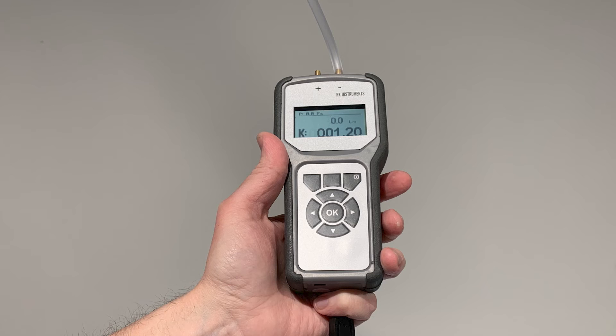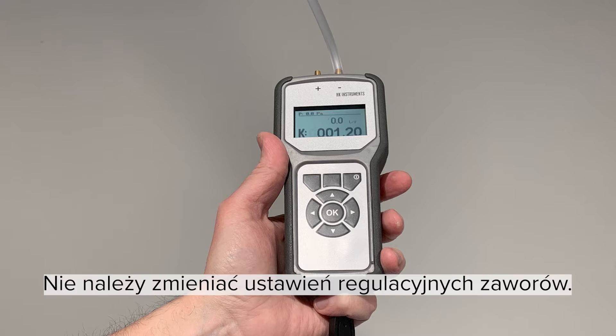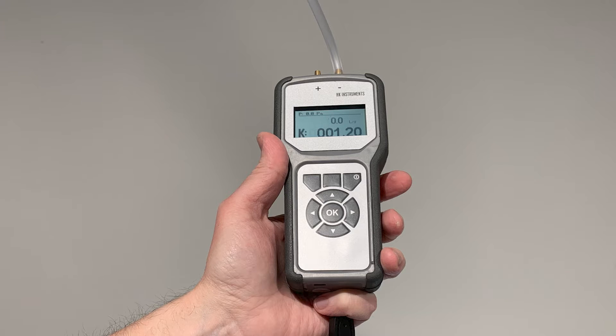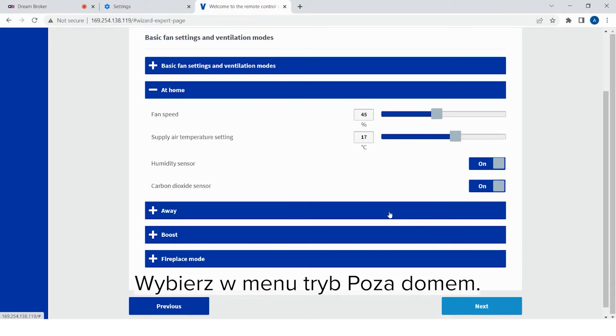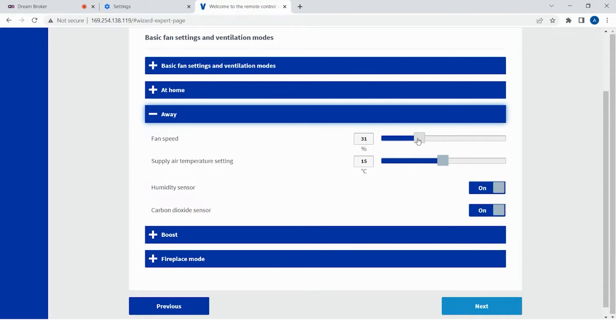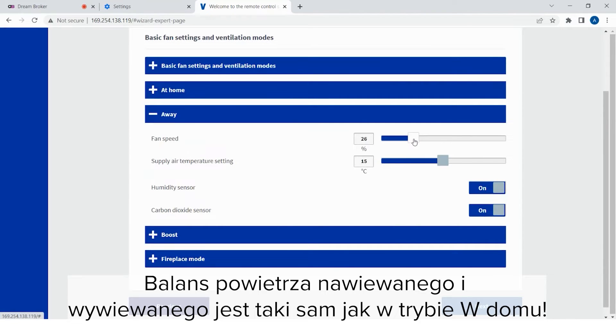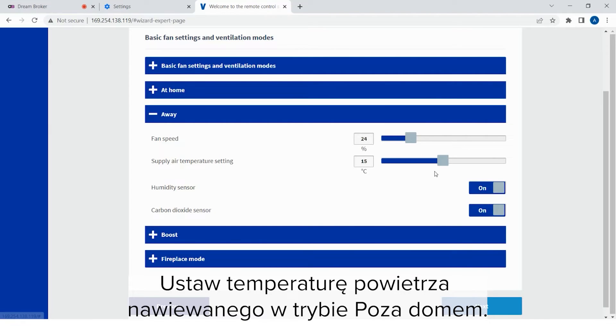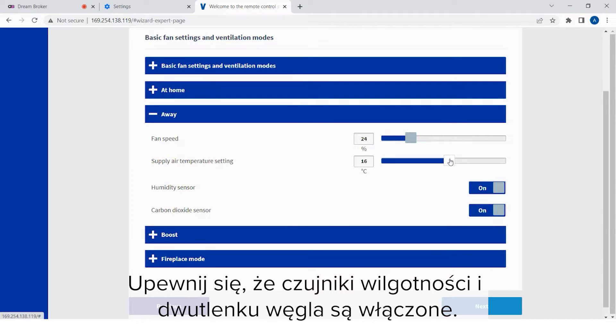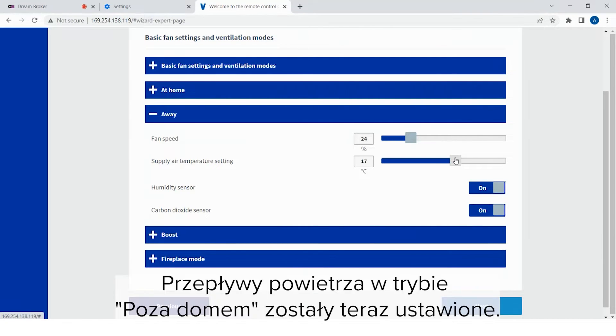Ensure that the humidity and the carbon dioxide base controls are turned on. Adjust the supply and the extract air flows of the away mode. Measure the air flows from the supply and the extract air valves. Do not change the adjustment settings of the air valves. Select away in the menu. Set the fan percentage of the away mode. The supply and extract air ratio is the same as the at-home mode. Set the supply air temperature of the away mode. Ensure that the humidity and the carbon dioxide base controls are turned on. The air flows of the away mode have now been adjusted.